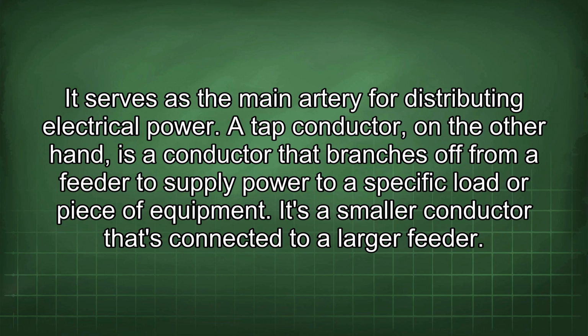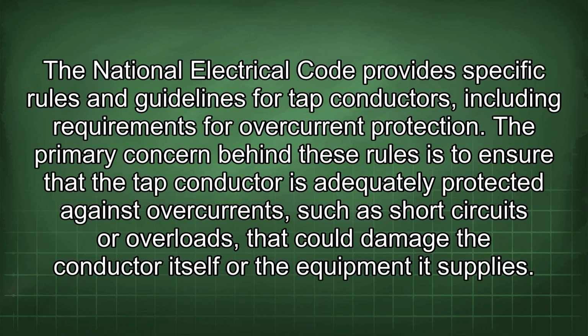A tap conductor, on the other hand, is a conductor that branches off from a feeder to supply power to a specific load or piece of equipment. It's a smaller conductor that's connected to a larger feeder. The National Electrical Code provides specific rules and guidelines for tap conductors, including requirements for overcurrent protection. The primary concern behind these rules is to ensure that the tap conductor is adequately protected against overcurrents such as short circuits or overloads that could damage the conductor itself or the equipment it supplies.